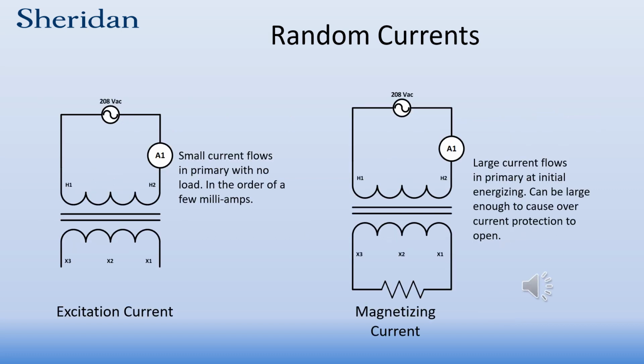Okay, so let's have another look at these random currents. Small currents can flow in the primary with no load on the secondary, usually in the order of a few milliamps. However, keep in mind that the larger the transformer, the larger these excitation currents can be.